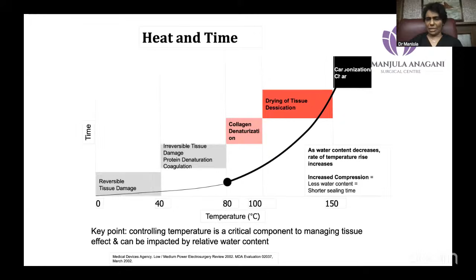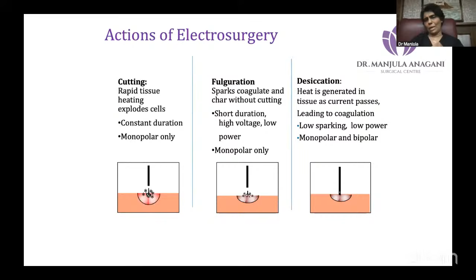When there is less water content, a shorter sealing time is used. So what does electrosurgery do? It cuts, it fulgurates, it desiccates. Cutting is by monopolar only, where the electrode doesn't touch the tissue, and there is rapid heating and an explosion of the cell. Fulguration is also by monopolar, and it is short duration, high voltage. But desiccation is by both monopolar and bipolar.